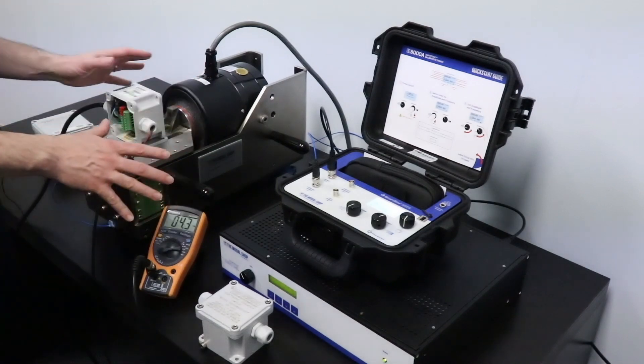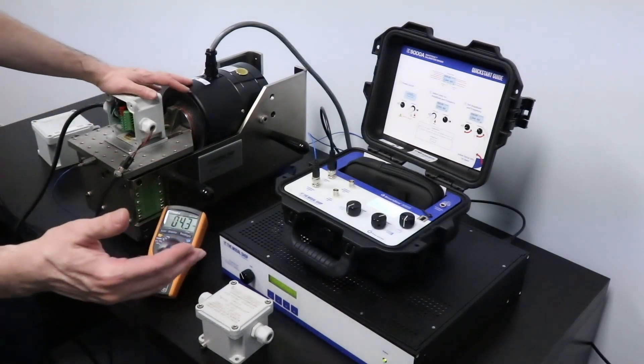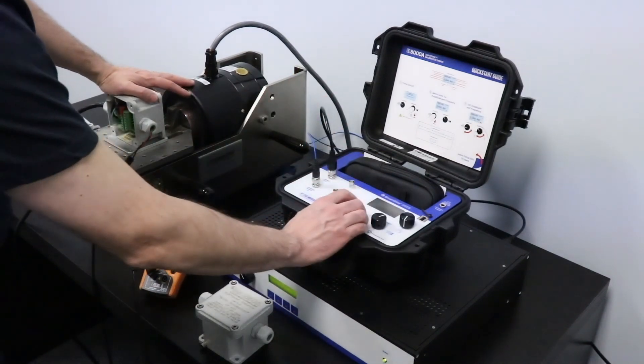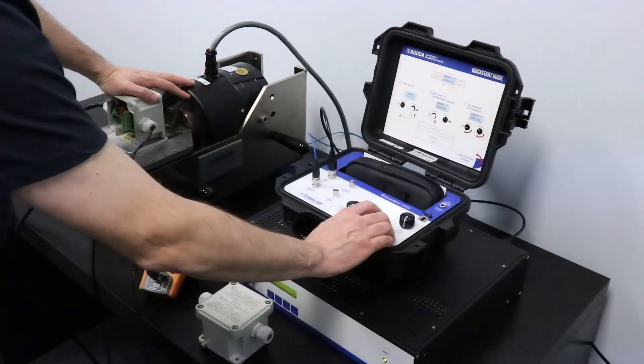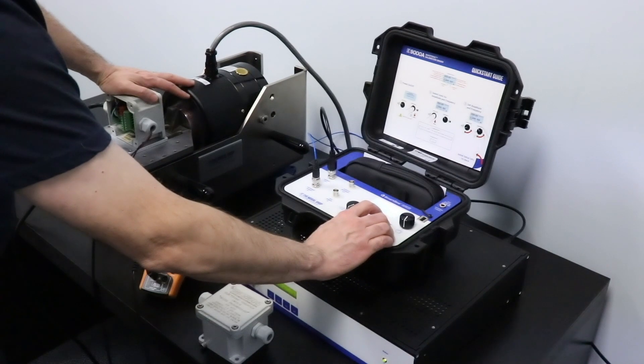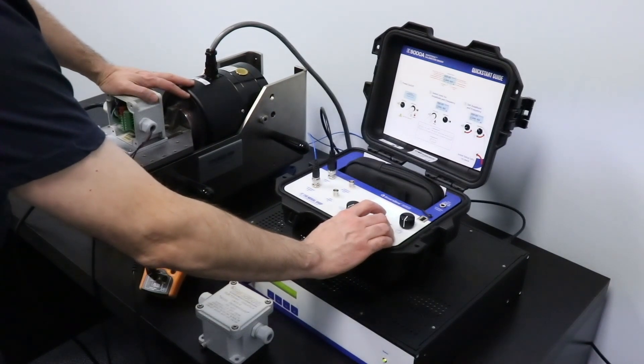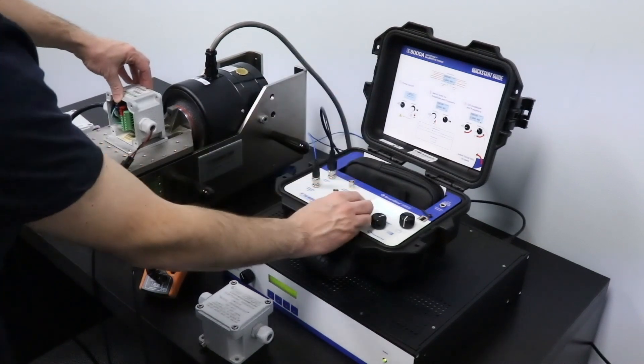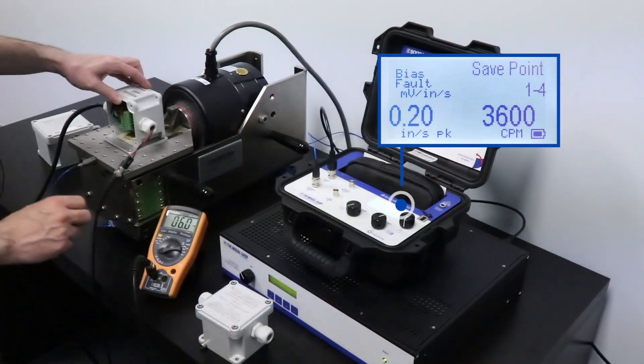This is a 4-20 milliamp device. So right now there's four milliamps, no vibration. And I'm going to turn my shaker table on. So currently everything is running as expected. 3600 RPM and 0.2 inches per second, which is about five millimeters per second peak.